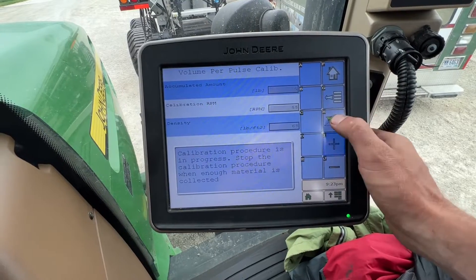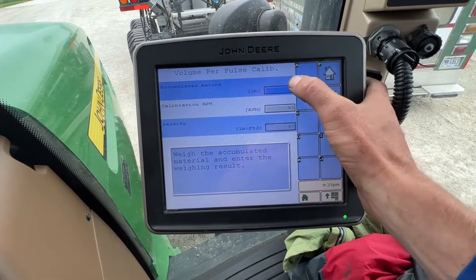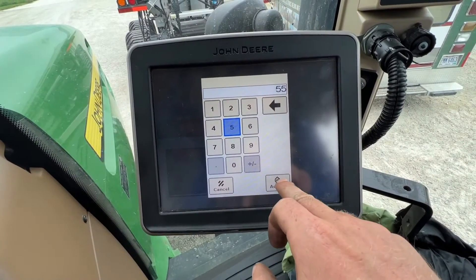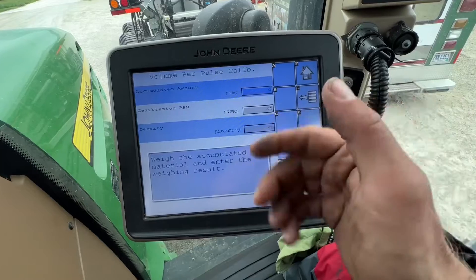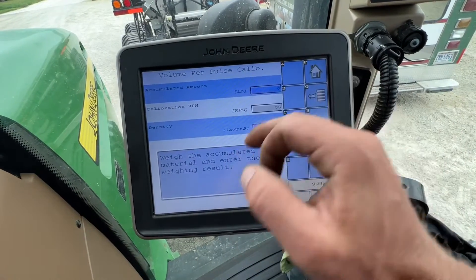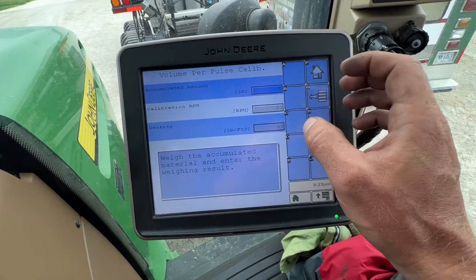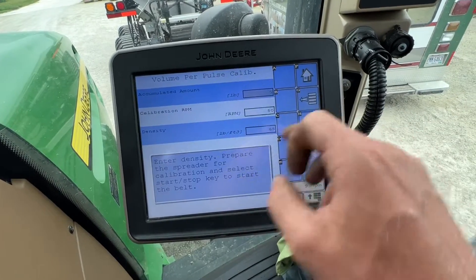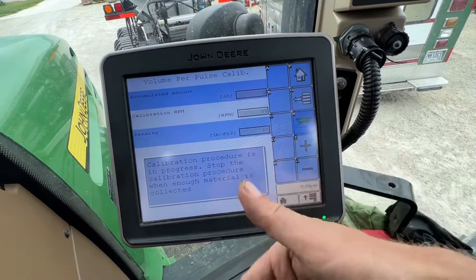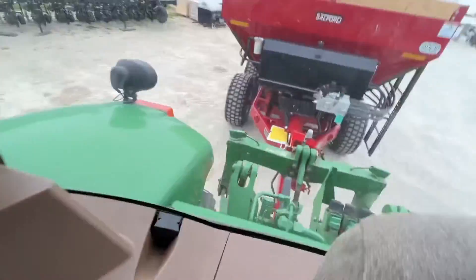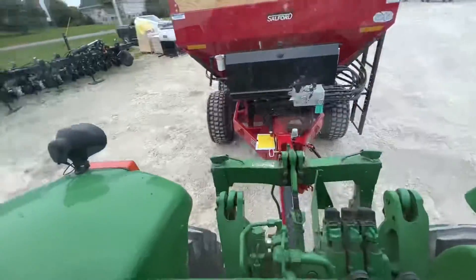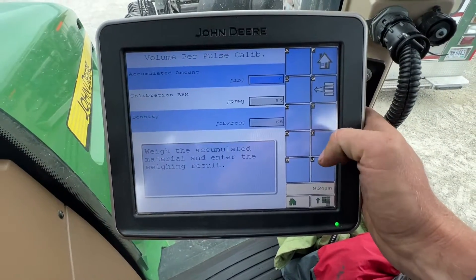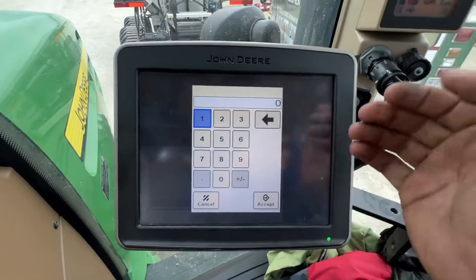You basically collect what it puts out. You hit stop, enter in how many pounds you caught — let's say we caught 55, but I'm not going to do that because it would change my cal factor. Then it will correct itself. You basically just hit the button until you catch your desired amount, so it would be spinning right now — just spinning — and then you hit this button when you want to stop.